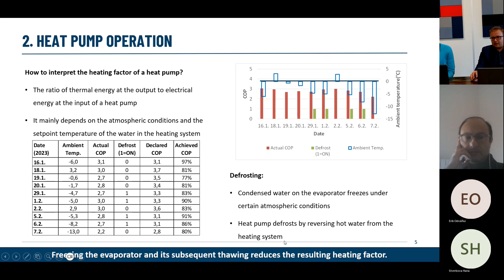So lots of tuning, but it tells you that essentially you have to take the data sheets with a grain of salt, to put it mildly. But anyway, the key takeaway is, if you think of a typical day when you operate the heat pump and you want to gain maximum out of it, you understood from the previous slide that the lower the ambient temperature and the greater the set point temperature of the water circulating in your system, the worse the coefficient of performance is going to be.